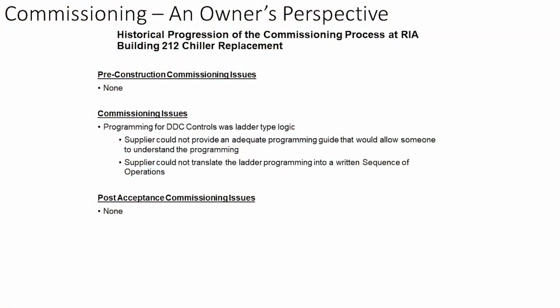Commissioning agent was a subcontractor to the general. In this case, the general was a mechanical contractor. We had local commissioning agent and balancing agent, and they were the same as before. And they were separate firms, so they were familiar with what I was after. We didn't have any issues during commissioning. We only came across one problem during the actual commissioning, and that was the programming in the DDC controls. This was a different manufacturer than we normally used on the island. Not the chiller manufacturer, but the actual DDC control contractor.